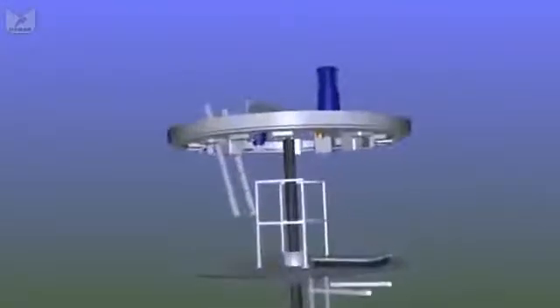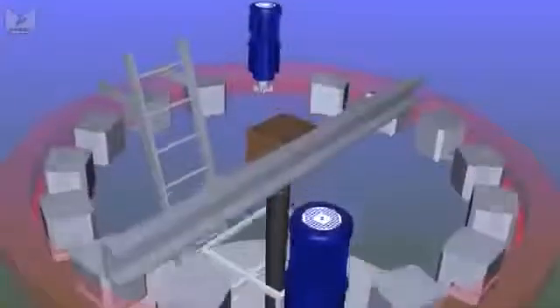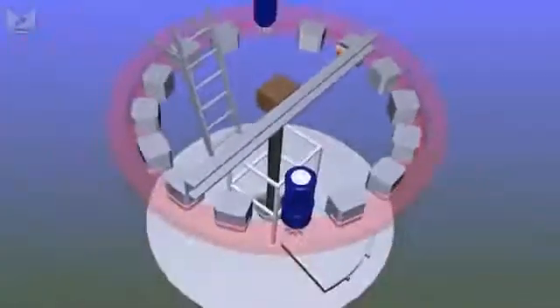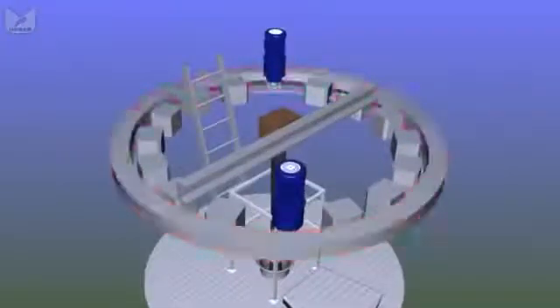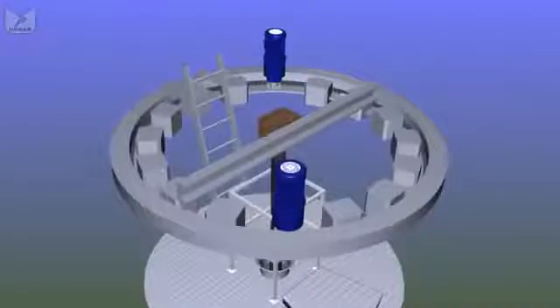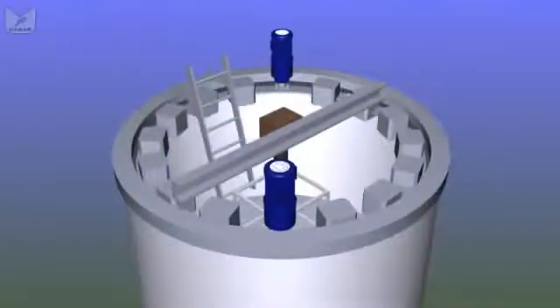Then it starts looking very much like the smaller turbine did. We have a yaw ring bolted to the underside of the nacelle, joining it to the top of the tower. A series of disc brakes run around that yaw ring to lock it in position when the wind isn't changing direction, and when it is, we have a series of either electric or hydraulic motors that rotate the entire mechanism around on the top of the tower.